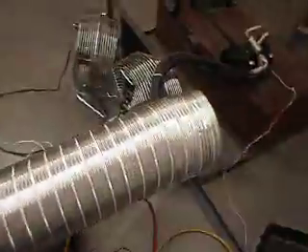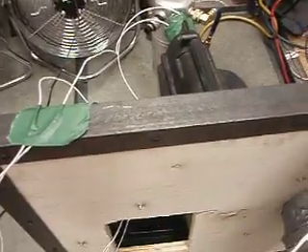And that explains my heat transfer test. I'm using equipment from work. This Fluke Hydra-Series 2 has 10 temperature detectors. I have three running to the inlet air — they're inside of here. And I have three running to the outlet air, because this will give me my heat transfer across the evaporator of the air.